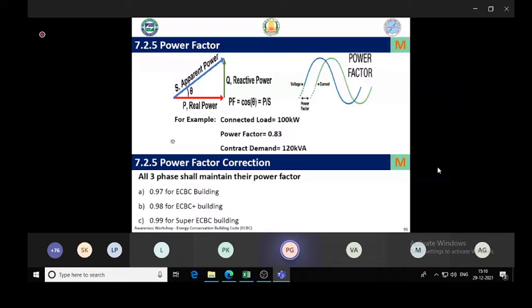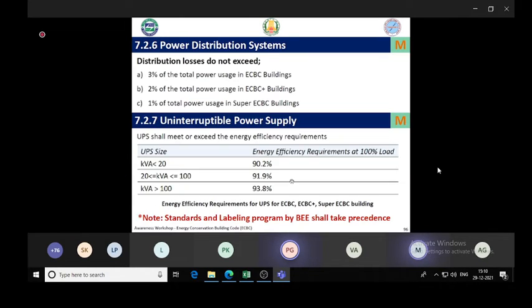Okay. In terms of power factor, it should be maintained between 0.97 and 1. This is mandatory. Sufficient capacitors should be provided. And in terms of the electrical cabling design, the code specifies the maximum allowed cable losses. Cable loss should not exceed 3% for the basic compliance, and 2% and 1% for the higher levels of compliance. So cable sizing should be done and calculation should be used to demonstrate that at full load, cable loss will not exceed 3%.